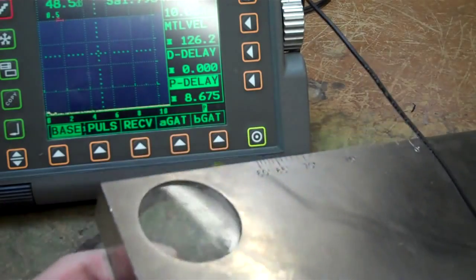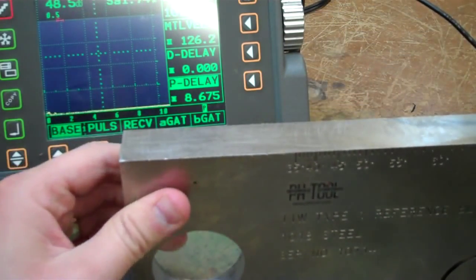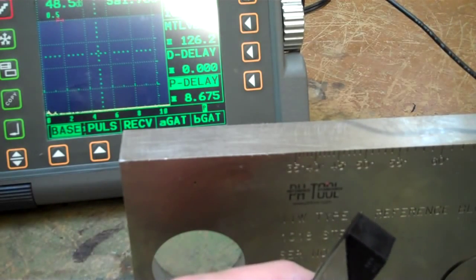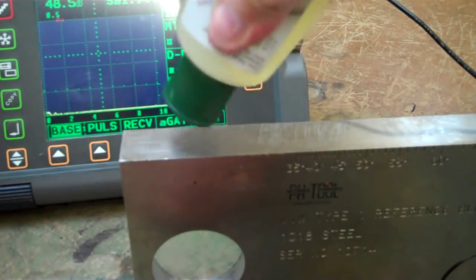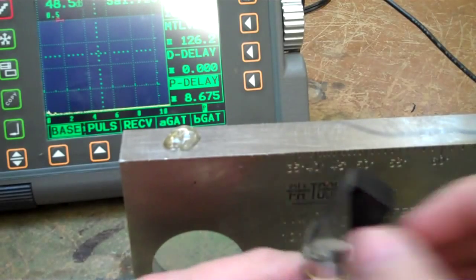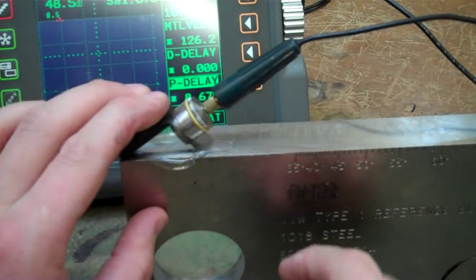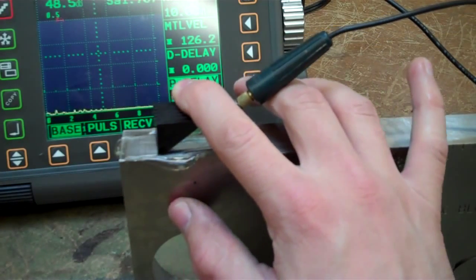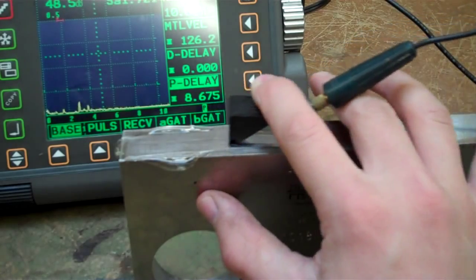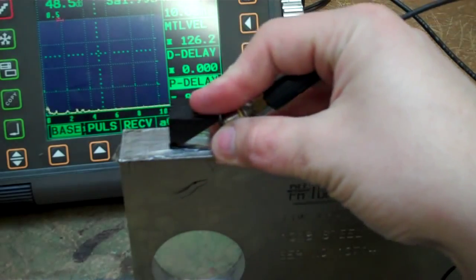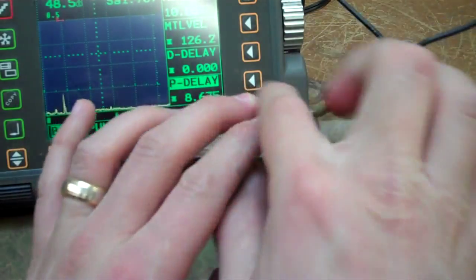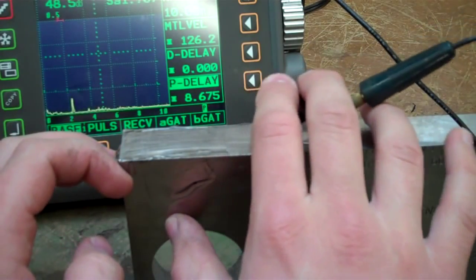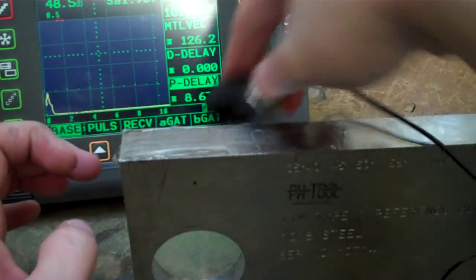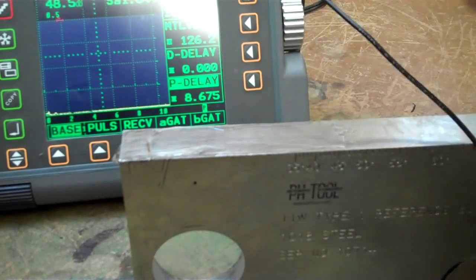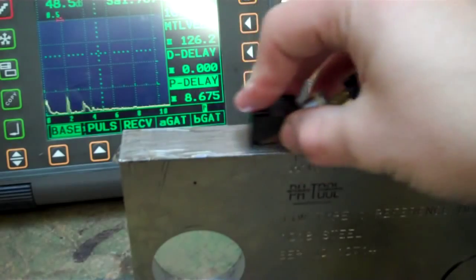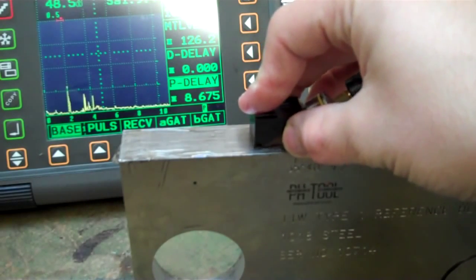Then the last part, part 4, says check your transducer or set your sensitivity using the 60 thousandths hole. We're going to do that right now. So set our, right there, whoa, that's plenty of couplant. Okay, we're going to set our sensitivity. So I like to start past the edge of the block. Okay, looking at the screen, back up until we see a signal jump up. Whoops. Help if I didn't lose the couplant between the two. Back up. There's our signal right there, about 2 inches. Okay, which should coincide with the 70 on the block, but the 70's on the other side over here. Alright, so there it is, about 2 inches.